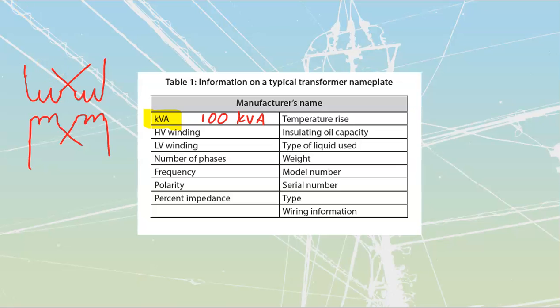What I would do is say that this whole side over here is good for 100 kVA, but each of these two halves is good for 50 and 50, which gets me to that grand total of 100 kVA that I'm going to have out of that transformer. We can then choose to connect in series and parallel. We're going to look at all of that stuff on our connections later on.